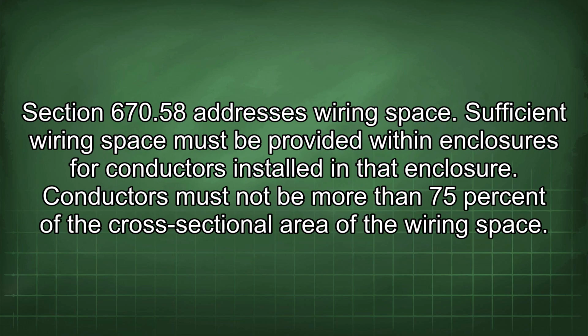Section 670.58 addresses wiring space. Sufficient wiring space must be provided within enclosures for conductors installed in that enclosure. Conductors must not be more than 75% of the cross-sectional area of the wiring space.